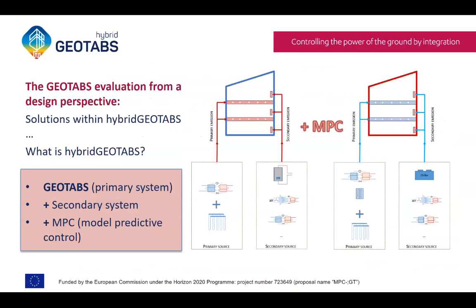And how do we do that? With the third element of the hybrid GEOTABS, the MPC, or model predictive control. That should guard the operation of the system so that the secondary system does not work when it is not needed, should anticipate, and should put the most energy supply on the primary system.